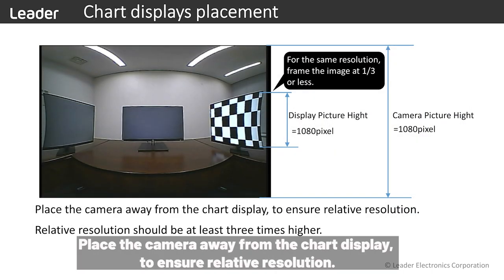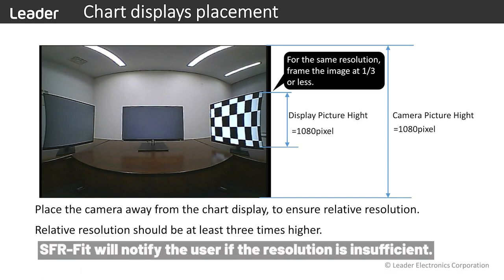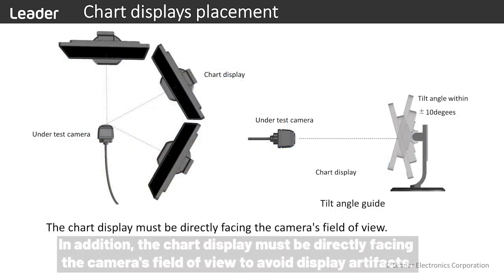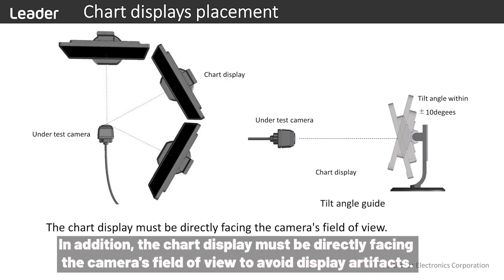Place the camera away from the chart display to ensure relative resolution. SFR-FIT will notify the user if the resolution is insufficient. In this case, move the camera further away from the display or use a higher resolution display. In addition, the chart display must be directly facing the camera's field of view to avoid display artifacts.